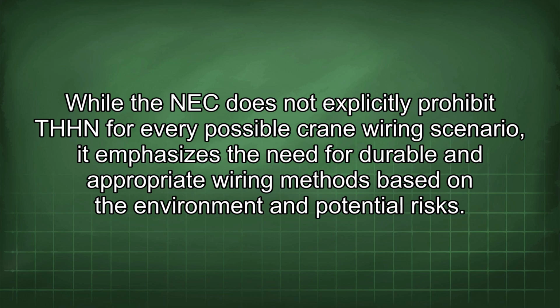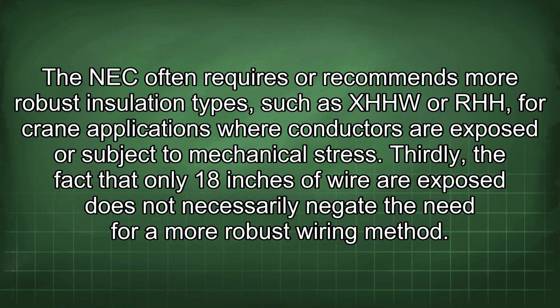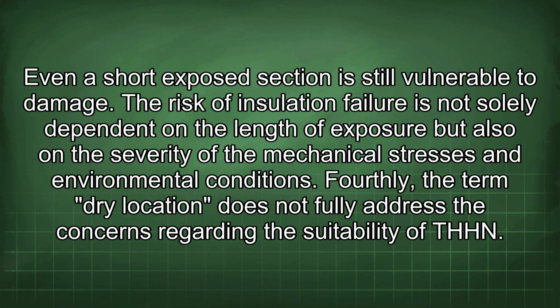While the NEC does not explicitly prohibit THHN for every possible crane wiring scenario, it emphasizes the need for durable and appropriate wiring methods based on the environment and potential risks. The NEC often requires or recommends more robust insulation types, such as XHHW or RHH, for crane applications where conductors are exposed or subject to mechanical stress. Thirdly, the fact that only 18 inches of wire are exposed does not necessarily negate the need for a more robust wiring method. Even a short exposed section is still vulnerable to damage.